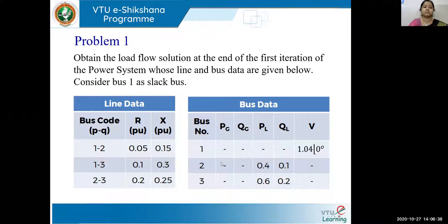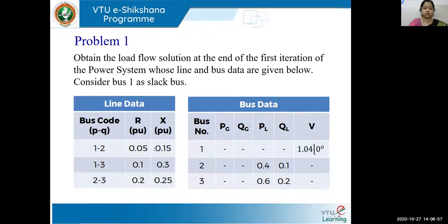The bus data tells us what type each bus is. Bus number one has voltage and angle given, so it is a slack bus. The next two buses have load values given, so they are load buses. The first step is to draw the network for this line data and then form the Y-bus.